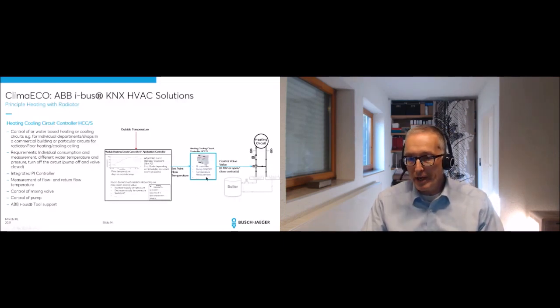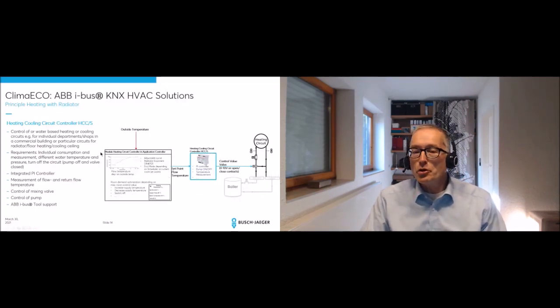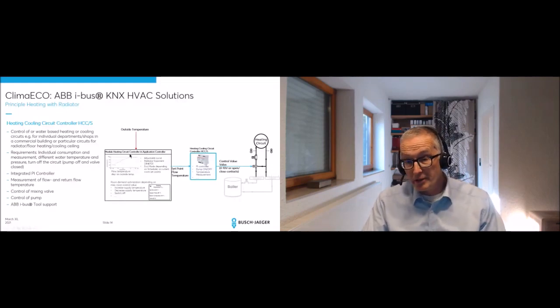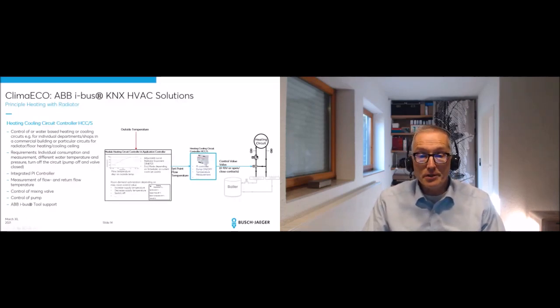How does this component know what is the right set point, the right temperature for this circuit here behind? This will be done then later in our application controller, and there's a software module behind to control everything the right way, depending on different parameters. Yeah, one parameter is, for example, the outside temperature. Of course, if it's very cold, and we talk about heating here in this example, then we need a higher flow temperature coming from the boiler or chiller to be supplied to the heating or cooling circuit. If there's no demand for heating in the circuit, all valves are closed, then we can also shut down maybe the boiler, or we can turn off the pump as well in the circuit. So different parameters, different adjustments are possible. And you see in the middle the so-called curve, supply temperature depending on outside temperature, which of course is dynamic. The lower the temperature is outside, the higher is the supply temperature.